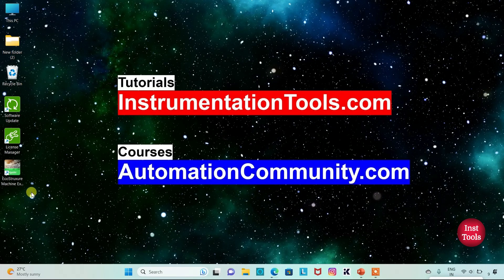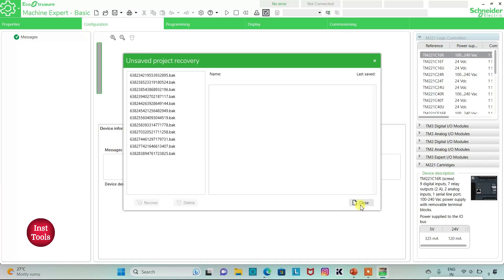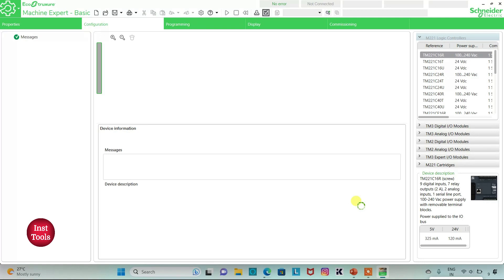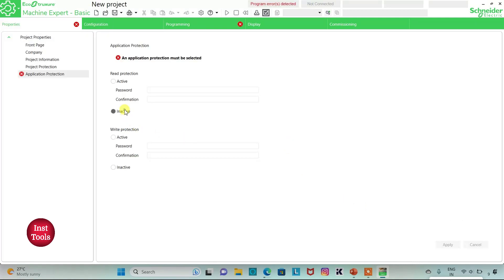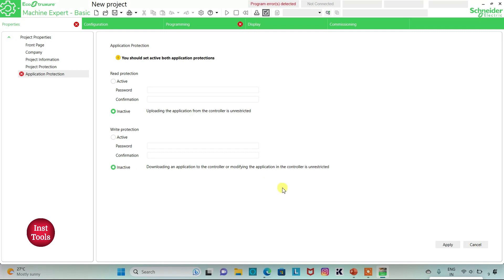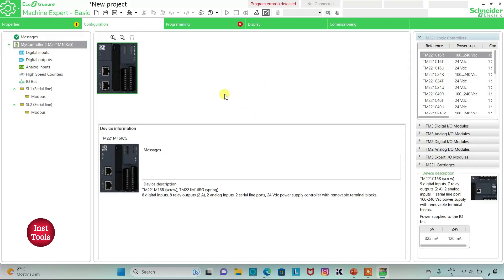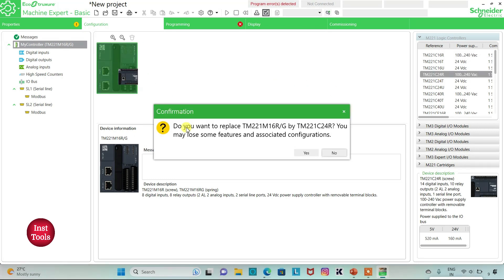I will open EcoStruxure Machine Expert Basic. I will keep read protection as inactive and write protection as inactive, then click on Apply. I will go to the Configuration tab, where we have to select a logic controller. I will be using TM221C24R. I will click on it, drag it, and click Yes to replace.